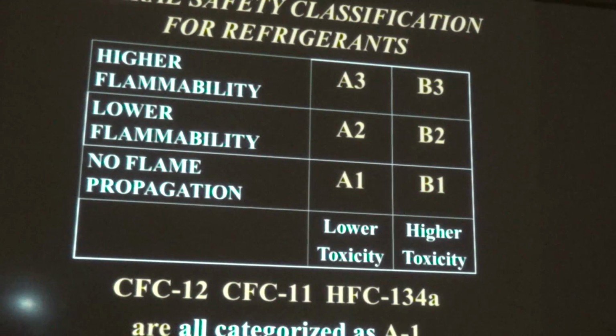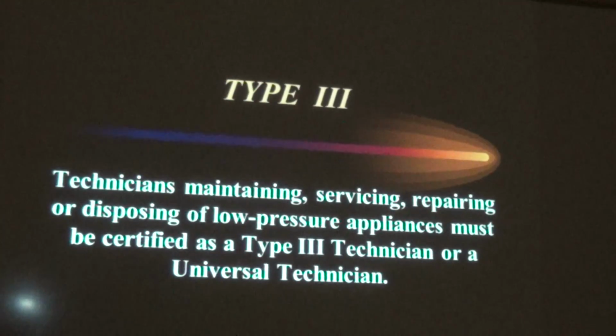R123 also you'll see is the one low pressure refrigerant that they're going to test you on. And R123 is also going to be the example refrigerant for the vacuum for chiller systems. Taking us right to Type 3. To work on a Type 3 appliance, which is a low pressure appliance, you have to have either Type 3 certification and or universal.